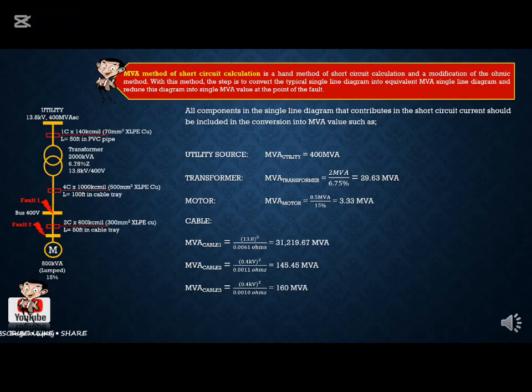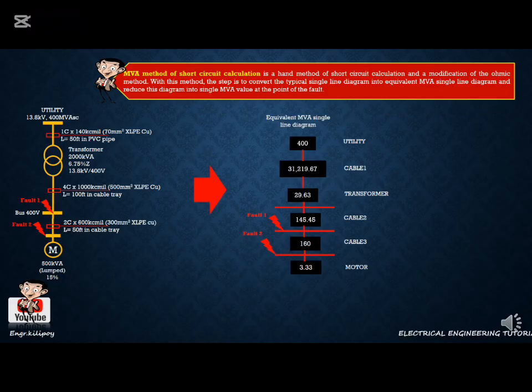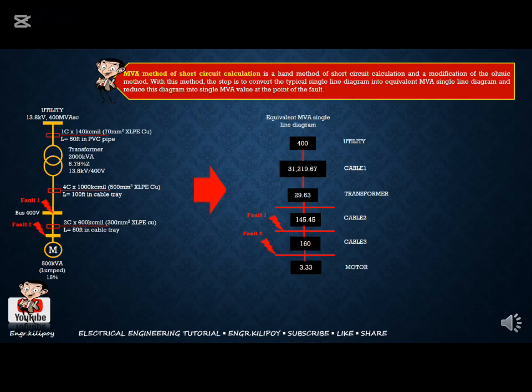For cable 1, ang MVA value niya is 31,219 MVA. For cable 2, 145.45 MVA, and for cable 3, 160 MVA. So nakuha na natin lahat yung components that contribute to the short circuit current. So pwede natin siyang ilagay sa MVA single line diagram. So from typical single line diagram, i-convert natin siya into MVA single line diagram.